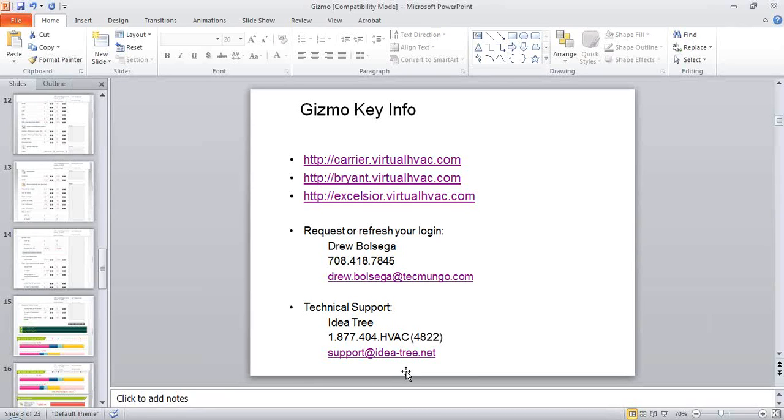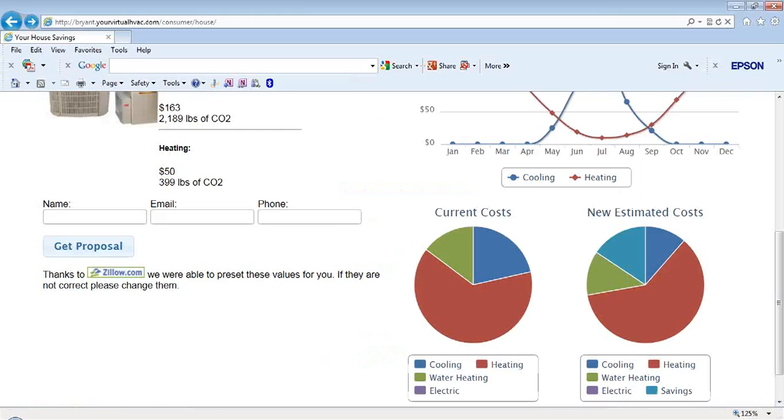And if I were to go one step further and put a variable speed ECM motor in, maybe it only costs me $80 or $90 a year. So $400 for the PSC, $120, $130 for the X13, $80 or $90 for the variable speed ECM. So there will be some electrical energy savings there. I do not currently have anywhere to change that in the model to account for that.